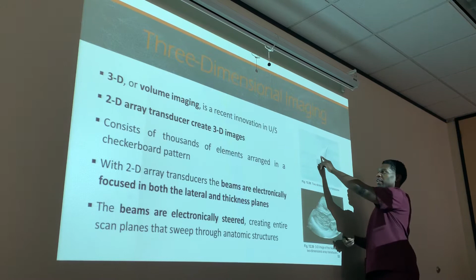Okay, so when the first pulse comes out, then after that the second one will be up or horizontal. And I'm sure that with the way the channel is created, it's arranged in a checkerboard pattern, so multiple elements are going to be sent out to create this. Remember it said it's electronically steered, so it's going to use multiple elements. So not only is it going to be focused side to side by using these elements, creating a curve this way to create the lateral resolution, but it's also going to be up and down, creating a curve this way to have good slice thickness resolution at the same time.